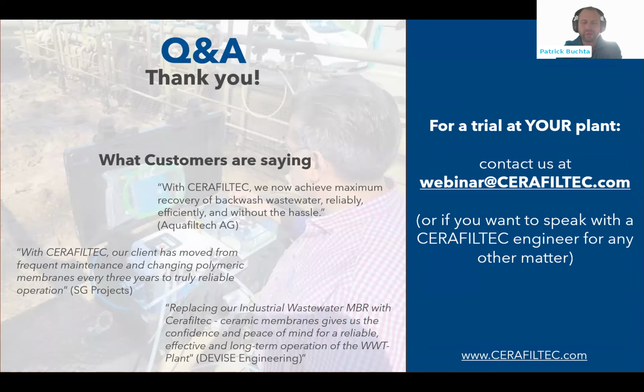Salt rejection, as in other technologies of this type, is actually zero. All salt is going through the filter. It's a pure mechanical filtration process, so only particles are rejected. Energy usage is below 20 watts per cubic meter of water. We only use the backwash, and we have aeration only during the backwash, which happens every 3 hours or so. So compared to other processes, it's absolutely at the lower end and comparable maybe also to pressurized in-out filtration processes. So nothing special here, but typically below 20 watts per cubic meter.